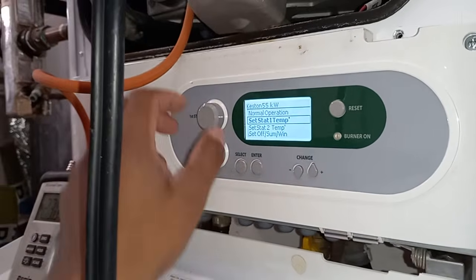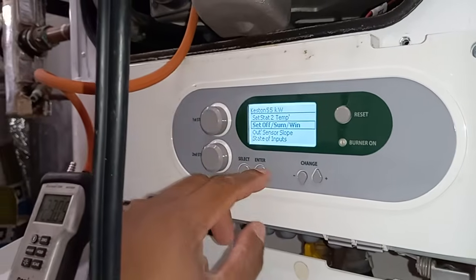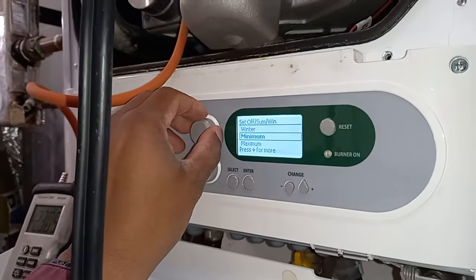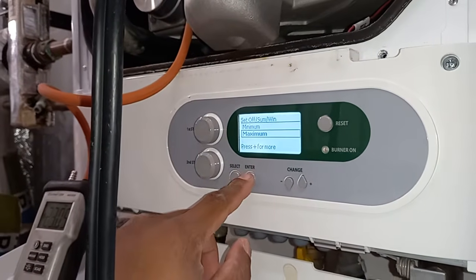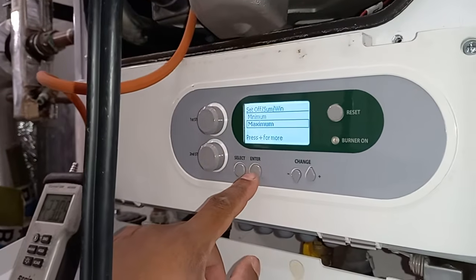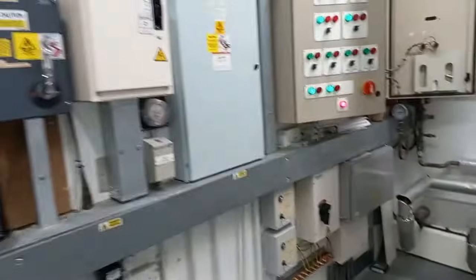And then now we need to get into service mode. Summer, winter, select - we're going to do maximum first. Always do maximum, high fire first, and then low fire. Hit enter. I'm going to go back to my BMS and create a demand, just in case that isn't enough over there.